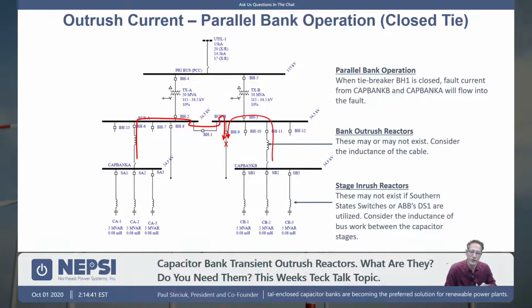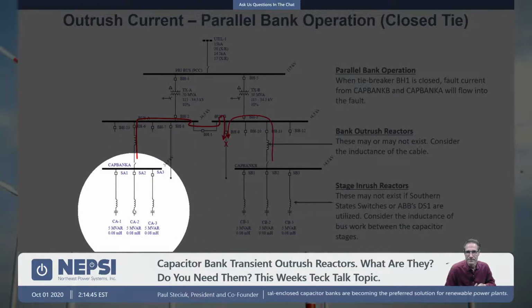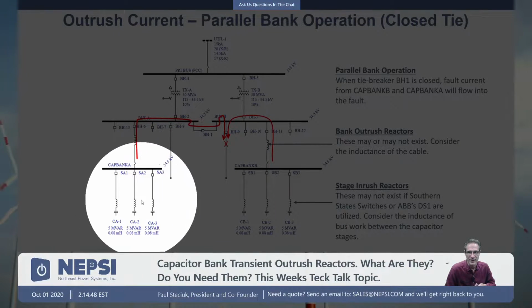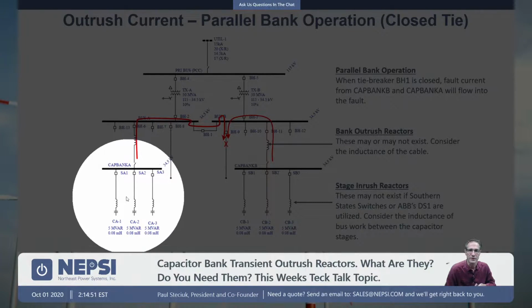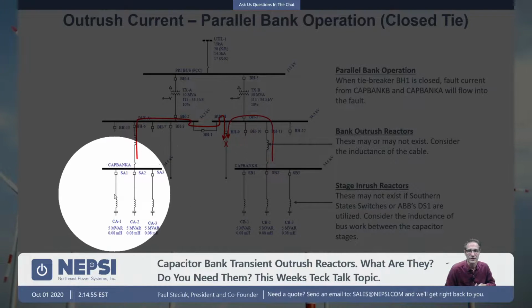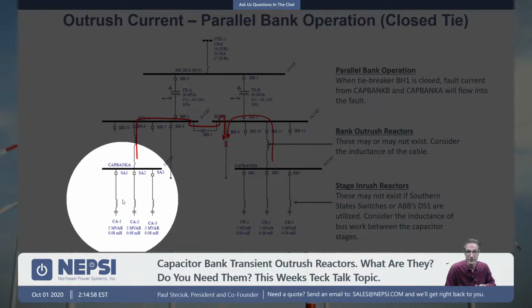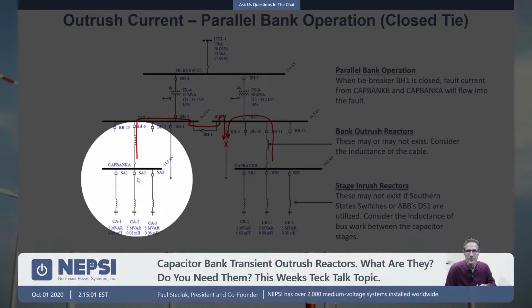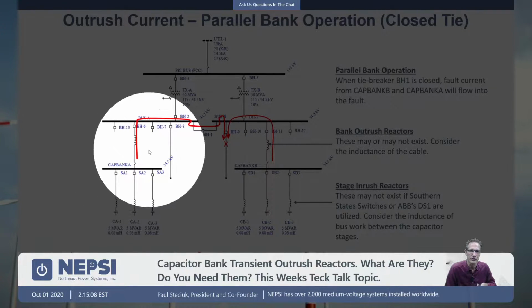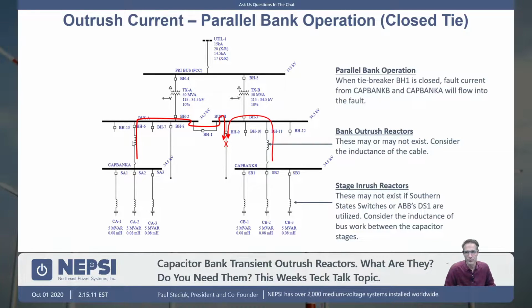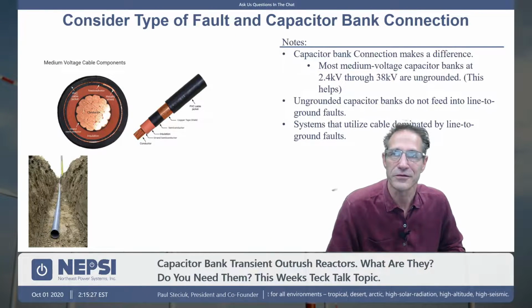The other thing you want to make sure you do is include any inductance in the capacitor bank itself. So if you have transient inrush reactors here, you can add that inductance. Basically, it'd be 1/3 of the inductance. Here we have 3 in parallel, so it'd be about 1/3 inductance, and that would help to increase the current flow. But this inductance here, 1/3 of that impedance will be added to this inductor here. And our spreadsheet tool essentially does this calculation for you, but the effect of having transient inrush reactors is to reduce the amount of inductance required by your outrush reactor. I hope that didn't confuse you, because it's a lot of information.